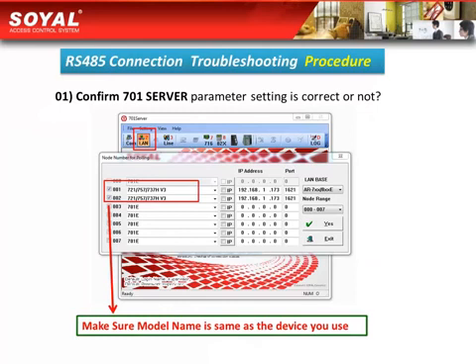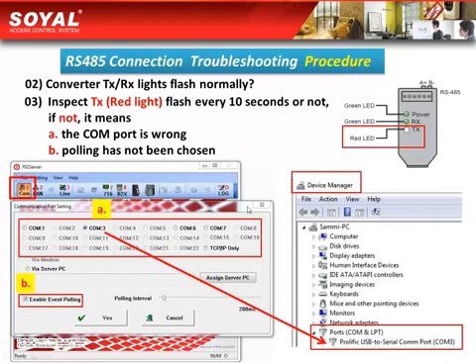If you find that your RS485 connection is unsuccessful, here are the solutions. First, go to confirm that the 701 server parameter settings are correct, and make sure that the model name you have chosen is correct. Second, observe the converter's TX or Rx light to check whether it is flashing normally or not.